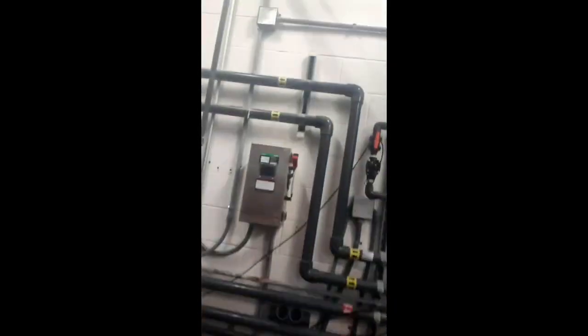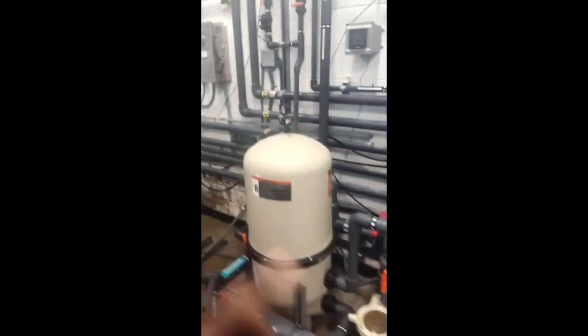Whenever I jumped out this flow switch, which you see the water pressure device right there, I'm a little confused as to if auxiliary device is the flow switch, because it has water pressure switch as well. And the reason why I think it is auxiliary device 1 is because whenever I jumped the switch out, or made common to normally open, the thing started up and the code went away. So I bought the part, $300 something to replace it.